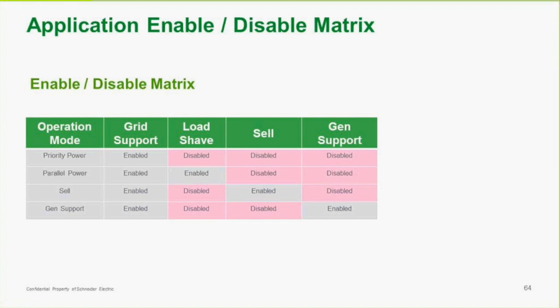So this is a matrix of the settings that are enabled and disabled. And depending on which mode you're using, what things are actually enabled and disabled. So priority power, we have grid support enabled, load shave disabled, etc. So it's a quick reference.